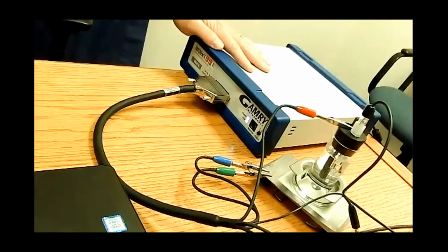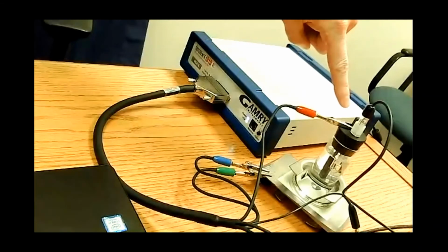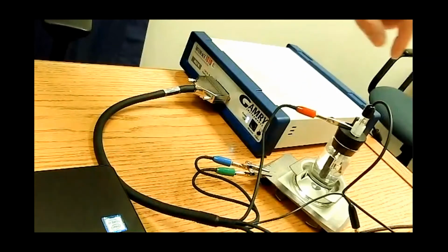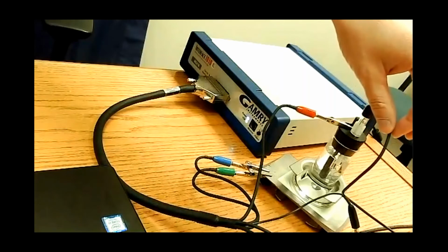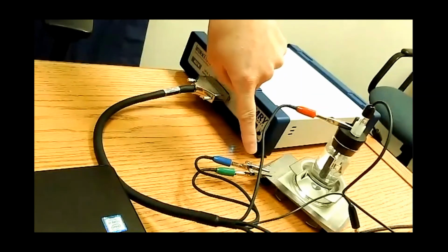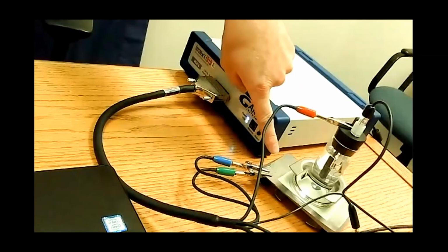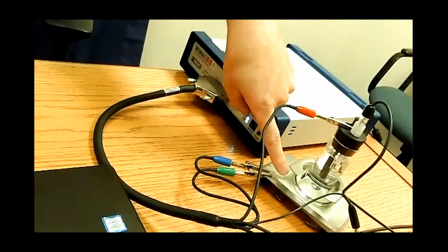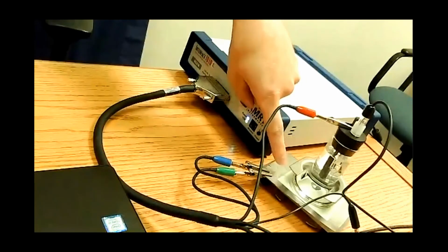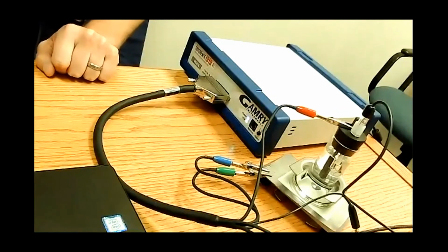Using the Gamry Interface 1010 potentiostat, I have a graphite rod as my counter electrode that you can see the red cable for here. Right here you can see the cable for our reference electrode, and then here are the two connections, working and working sense, that are connected to our metal sample. And you can see that I'm using a sample mask right there, that yellow piece. It's about a centimeter squared exposed there on the surface.